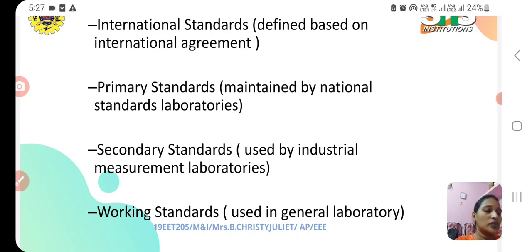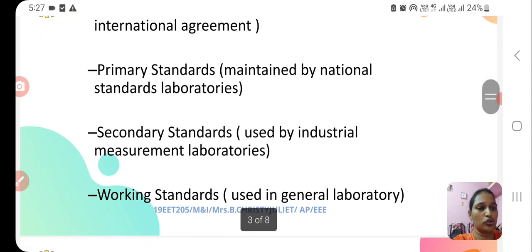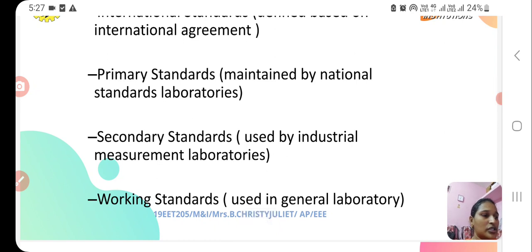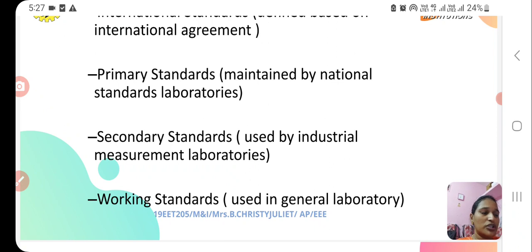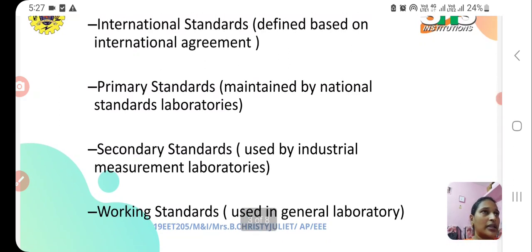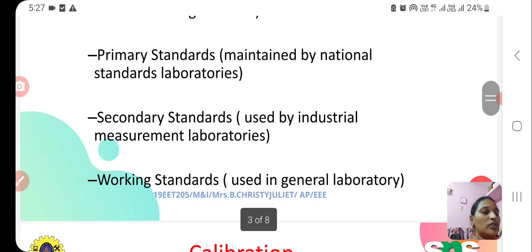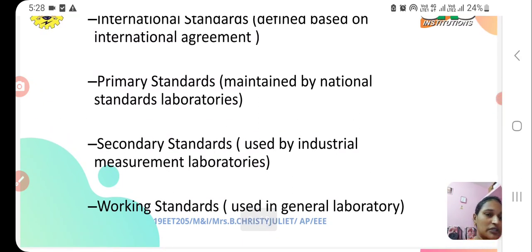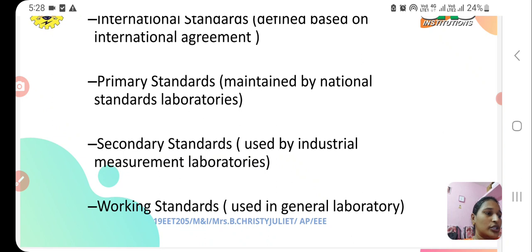Working standards are used for general purposes or in day-to-day use and are available in general or measurement laboratories. This standard is the primary tool for a measurement laboratory. Although international and primary standards are very accurate and give high precision, they cannot be used everywhere. The measuring devices we use regularly are working standards. They may be lower in accuracy compared to secondary standards, but are used to check and calibrate laboratory instruments for accuracy.